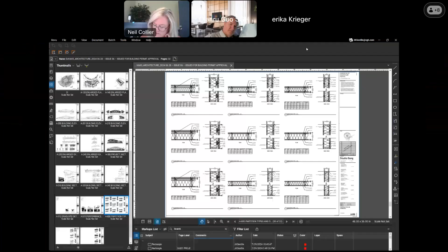Fire department access comes out of Chapter 5 of the fire code and its appendices. We comply with everything, but there's a portion left to the discretion of the responding authority that speaks to firefighter routes around the building perimeter. Ours are on the long side—to walk all the way around the outside to the far rear of the building, we've got that 290-foot dimension. To be fully prescriptively compliant with the fire code, the limitation from truck to the far point on the exterior of the building is 150 feet of walking. Ours is longer than that, but that distance can be expanded at the discretion of the responding fire captain.